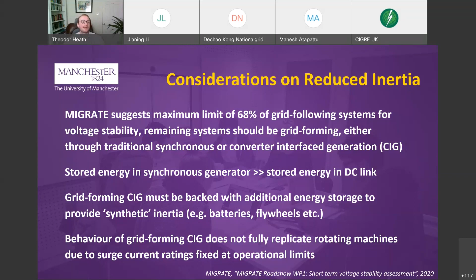The All-Ireland network, comprising the transmission networks of the Republic of Ireland and Northern Ireland, already has significant levels of system non-synchronous penetration, or SNSP for short, with a 65% limit at the moment, or that may have just changed to 75%, but they have committed to raising it to 75% and higher. This SNSP level includes instantaneous variable generation such as wind and PV, and HVDC interconnectors, as a percentage of the system electricity demand at that time.